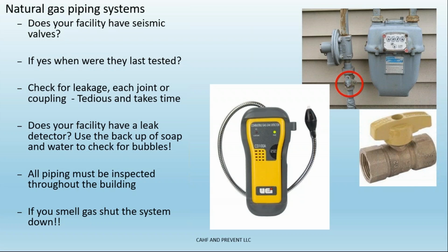If your building has a natural gas system, is it equipped with a seismic valve? If yes, when was the last time you tested it to make sure it actually works? Do you have systems in place to check leakage, such as a leak detector or other methods such as water and soap, to check on the joints for each gas pipe? The piping system will need to be checked for the entire facility. It is tedious and very time-consuming. Make sure you have some type of document to keep track of what system and locations were checked and cleared, repaired, or shut down. If you smell gas, turn the gas off and notify the utility or call 911 immediately.